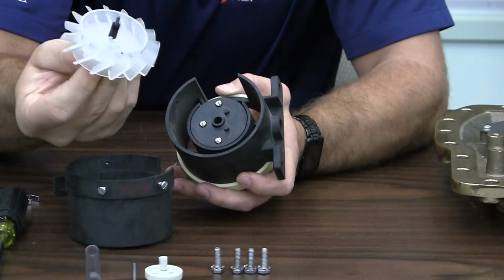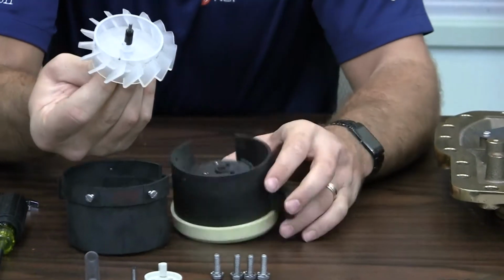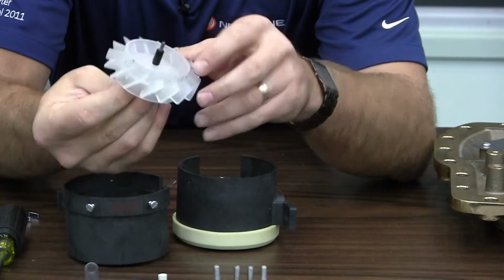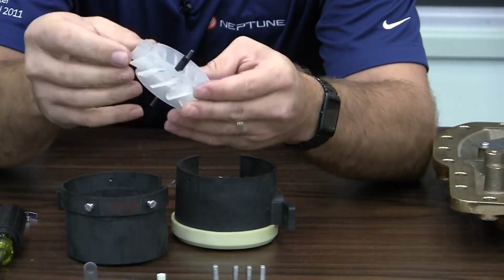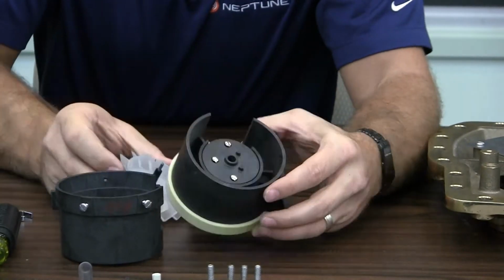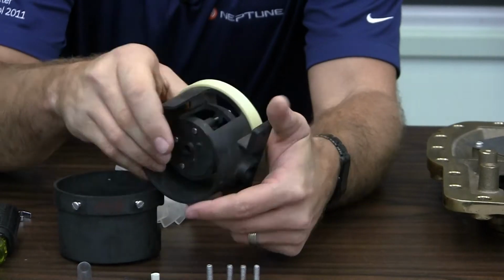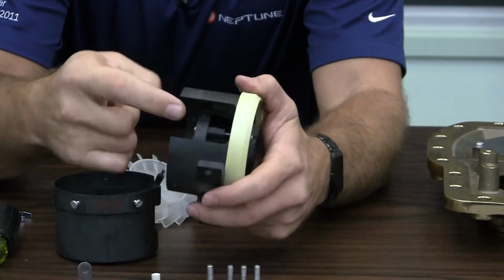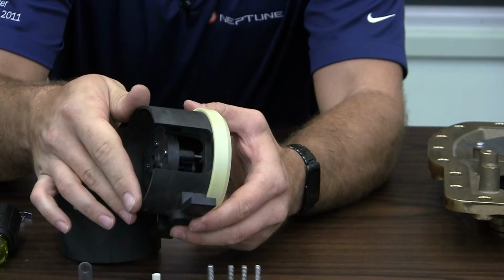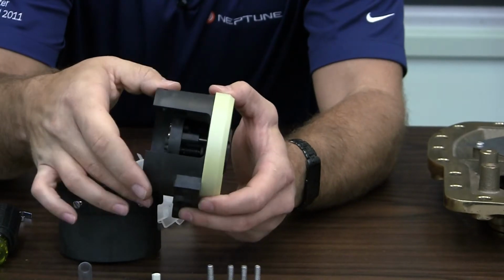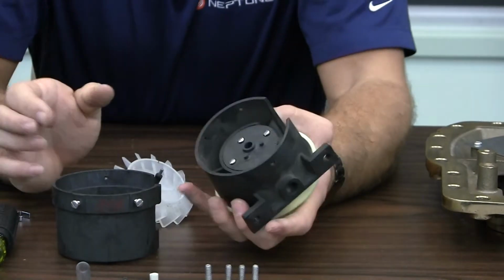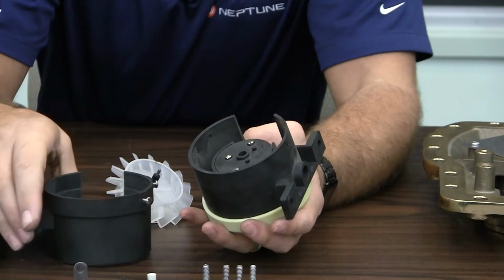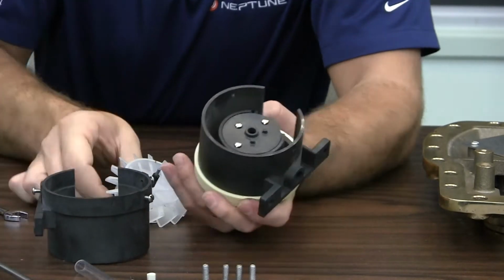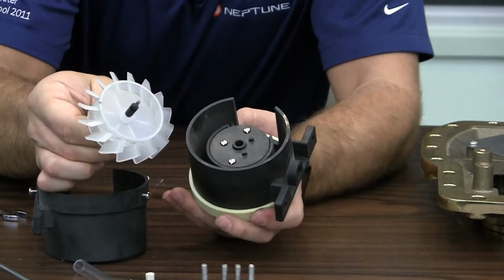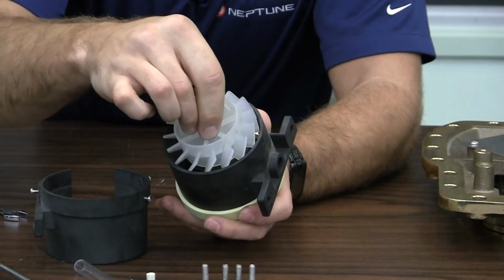If you pull the turbine out, or the rotor of the turbine out, you can see a geared portion of the rotor assembly, which mates with the gearbox on the outlet side. And you can see mine's cut away, exposing some of the gears inside of the gearbox.